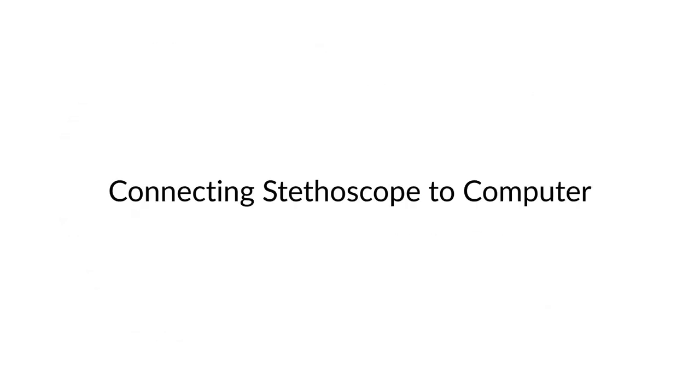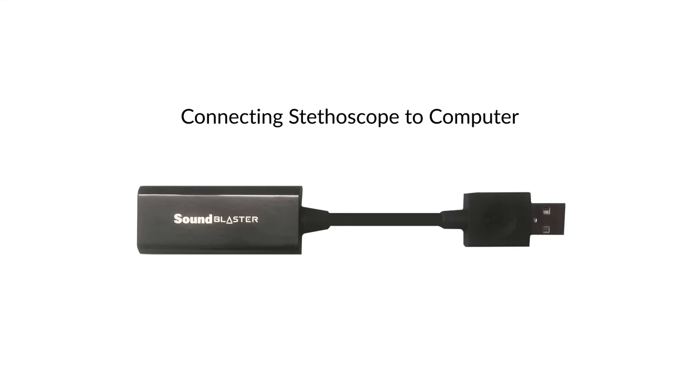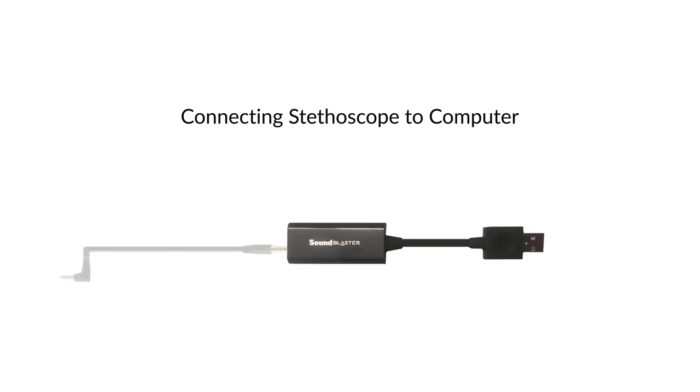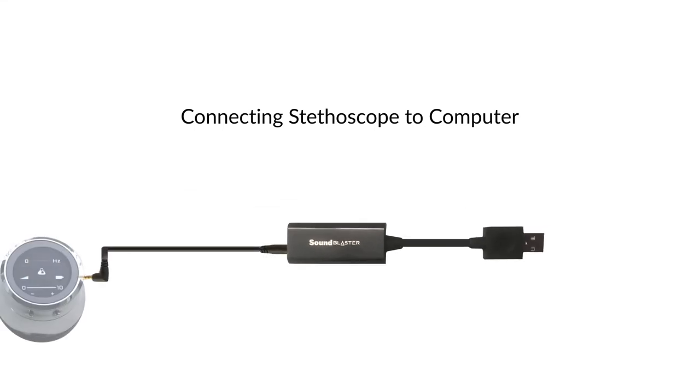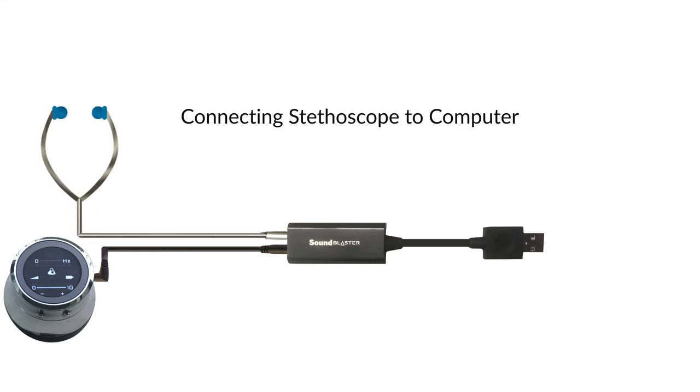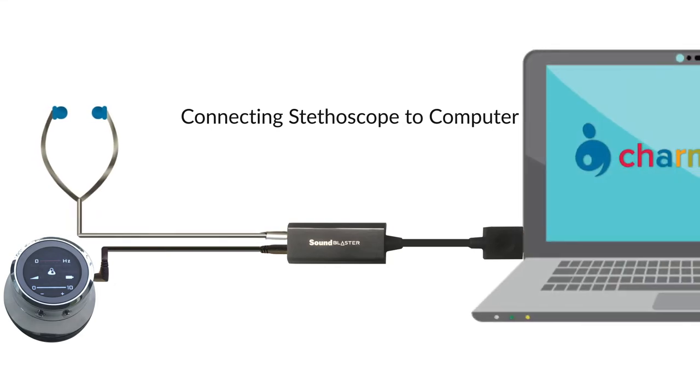Connect stethoscope to computer. You can connect the stethoscope to your computer, tablet, or mobile phone using the ThinkLabs mobile kit or the Sound Blaster USB adapter. The USB adapter is recommended while connecting the stethoscope to a computer. Use the longer cable provided to connect the stethoscope to the bottom left jack. Plug in the earphones to the top left jack. Plug in the USB adapter to the USB port of your computer.